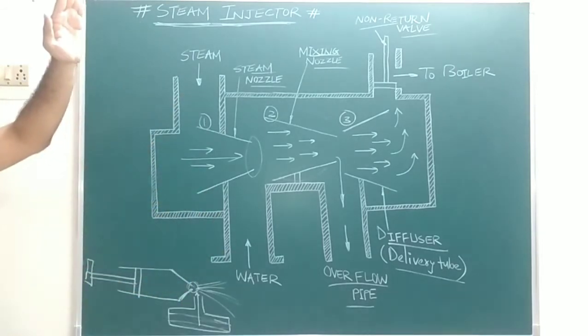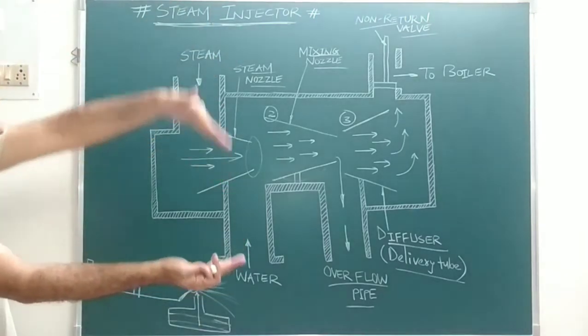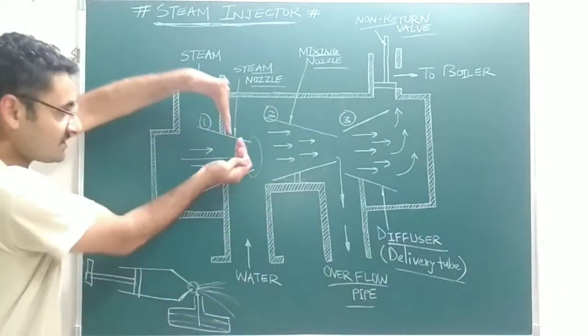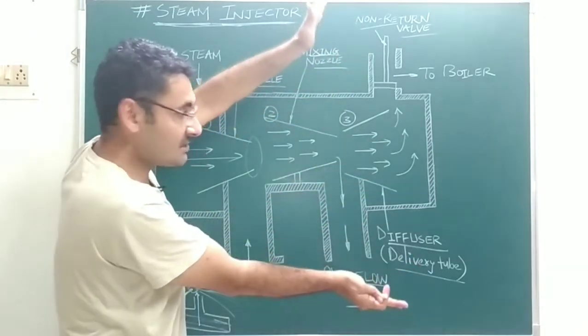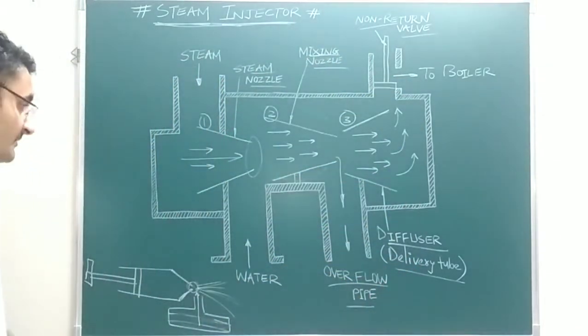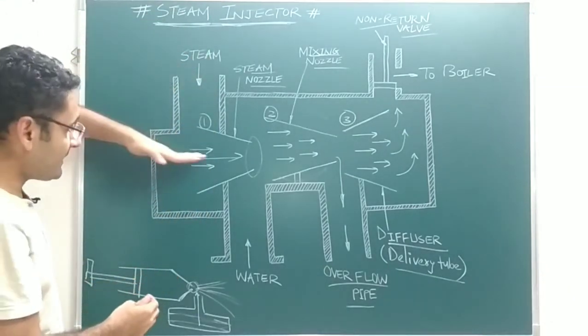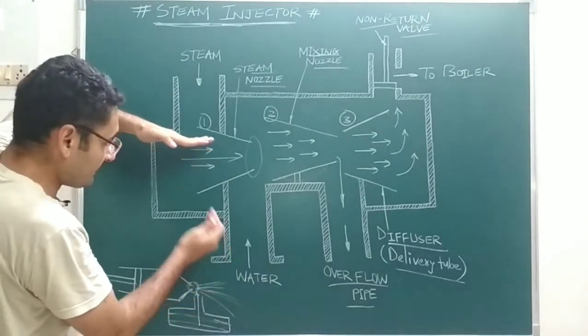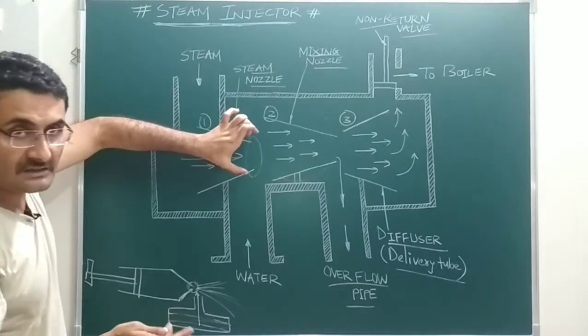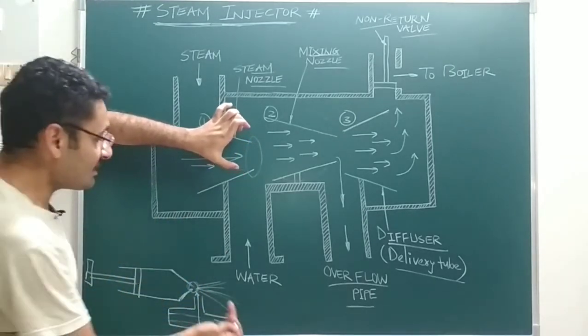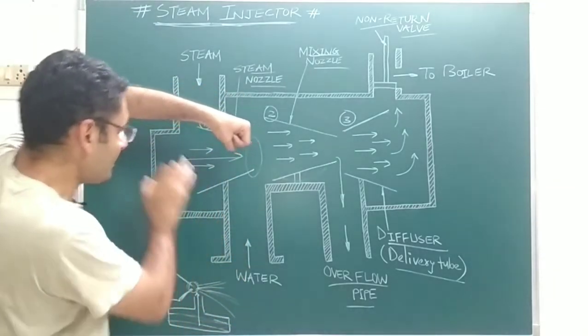Conversely, a diverging nozzle — a diffuser — increases the pressure. So to summarize: the converging steam nozzle increases velocity and decreases pressure, creating a suction effect that draws water upward. The diffuser increases the pressure. Steam from the first inlet enters the steam nozzle, velocity increases, pressure drops at the outlet, suction draws water upward.